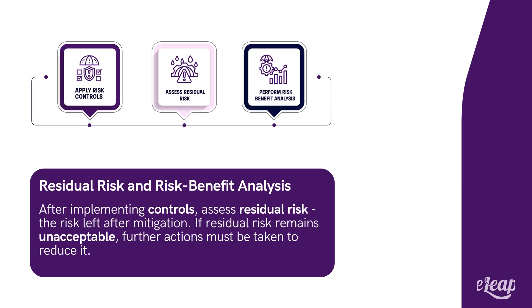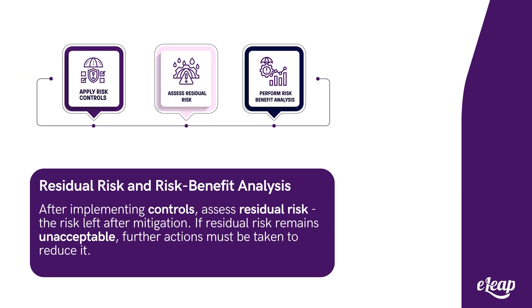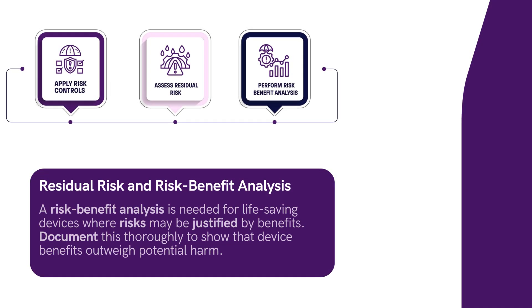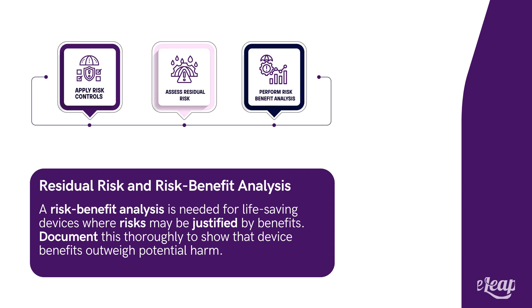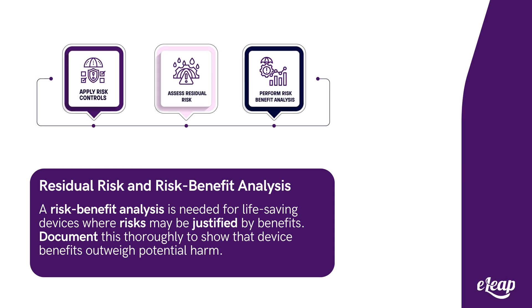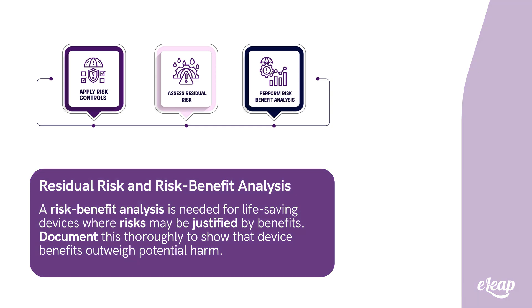Once controls have been implemented, it's essential to assess residual risk — the remaining risk after mitigation measures. If the residual risk is still unacceptable, further actions must be taken. In some cases, a risk-benefit analysis is required, particularly for life-saving devices where a certain level of risk may be justified by the benefits. This analysis must be thoroughly documented to demonstrate that the benefits of using the device outweigh any potential harm.